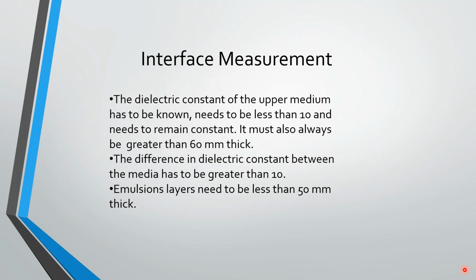So there's some basic rules of thumb. Now, these numbers are not cast in stone, but basic rules of thumb. The dielectric constant of the upper medium, we have to know what it is. Whichever medium is floating on top, we need to know what the dielectric constant is, and it has to be less than 10. It has to be at least 60 millimeters thick. The difference between the upper and lower layer has to be a difference of 10. So if our top layer is 5, our bottom layer has to be at least 15.